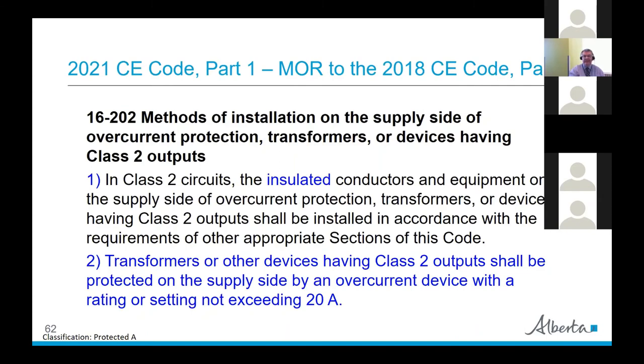In Section 16, the word 'insulated' was added for conductors. Also, in sub-rule two, it now says transformers or other devices having Class 2 outputs shall be protected on the supply side by an overcurrent device with a rating or setting not exceeding 20 amps — again reflecting the introduction of 20-amp branch circuits.